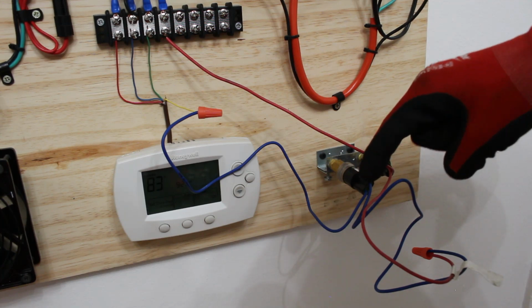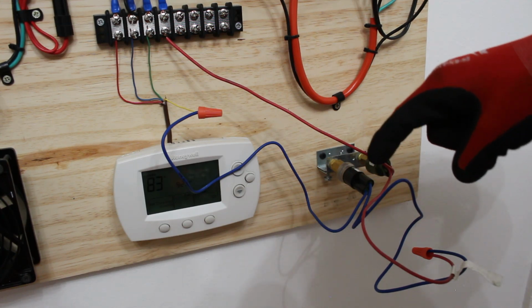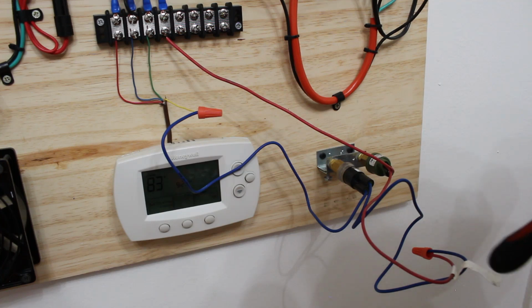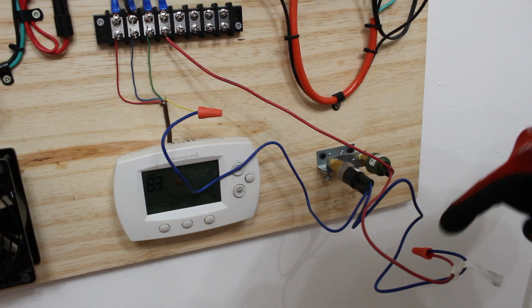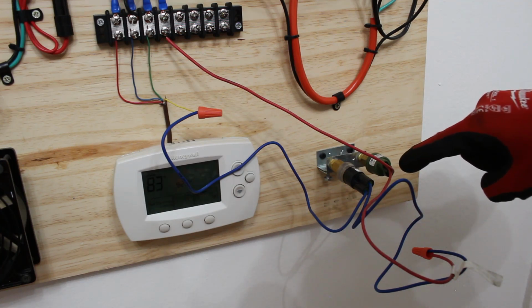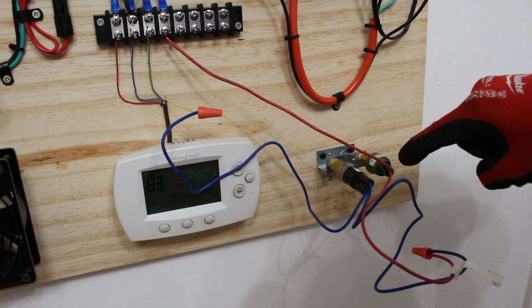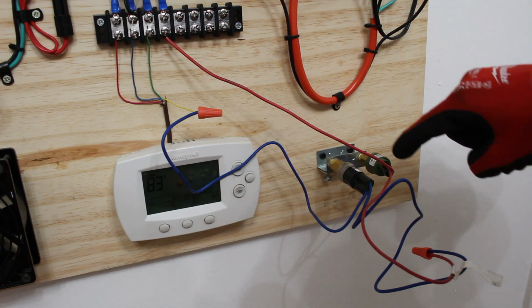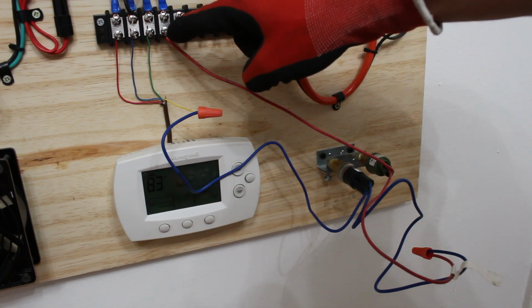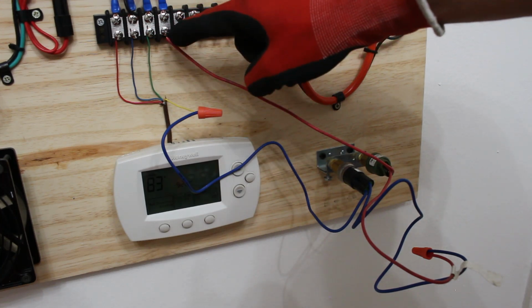There's one wire left on our pressure control, the low one. From there, that one is gonna get connected to one side of our high pressure control. Then we have one wire left for our high pressure control. And then that's going to go back to where originally the yellow wire was.